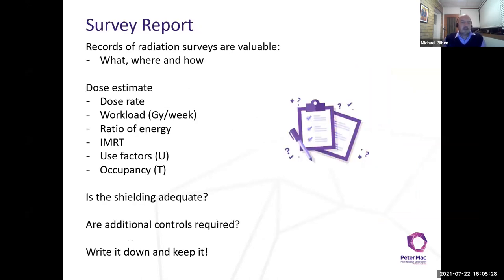So once you've selected your locations and you're confident that you're using an appropriate instrument and your measurements are going to be reliable and meaningful, you need to do the survey, of course, and then you need to write it up. This again is extremely important in my opinion. You might need to demonstrate to your direct supervisor, the hospital manager, the builder, the architect, or your regulator that you need to show evidence that that survey has been conducted and that that facility is safe to proceed.